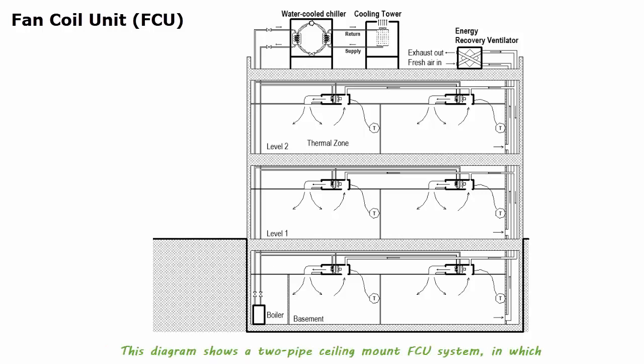This diagram shows a two-pipe ceiling mount fan coil unit system in which a fan drives the indoor air through the coil and back to the space. Each of the units only has one supply pipe and one return pipe. The pipes are connected to the chiller and the boiler. However, they run either hot water or chilled water, not both. It means the system either provides heating or provides cooling, so there is a lack of flexibility. All building areas must operate in the same mode. Heating some areas while cooling others is not possible with this design.